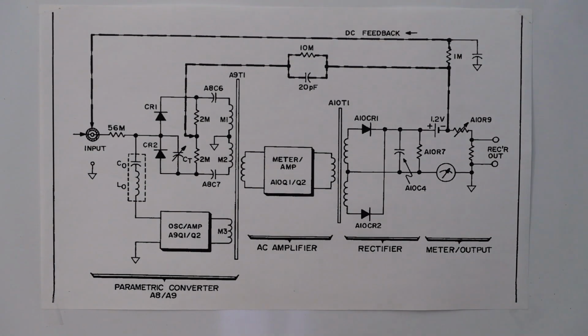So now we look in a little bit more detail at the entire instrument in a simplified block schematic with some critical components shown here. On the left side we have the parametric converter as we described earlier, and then we have the AC amplifier for the meter, and then the output stage which has a rectifier and the meter output. And there's also some feedback which I will talk about over here on the top. So looking at the meter itself, you have the resistance connected between the center point of this input to ground, and you have a 56 megohm resistor in series with the two picodiodes over here, CR1 and CR2.